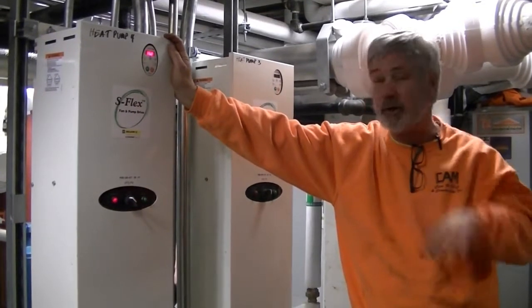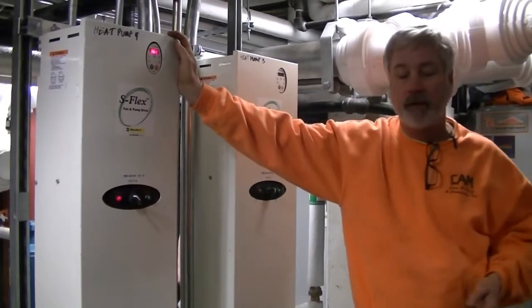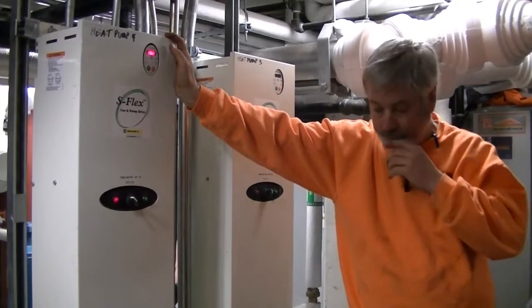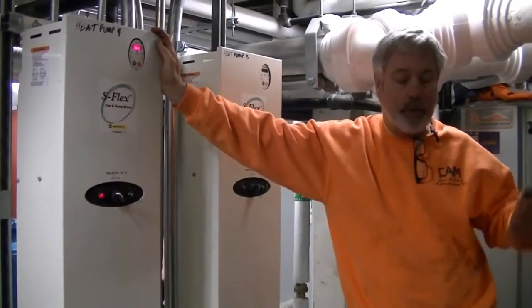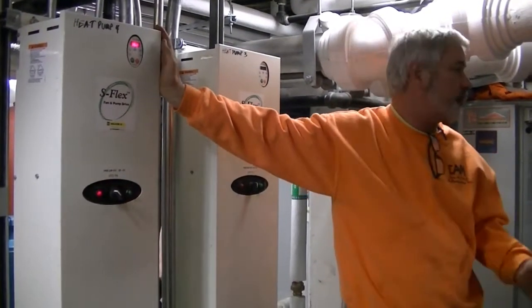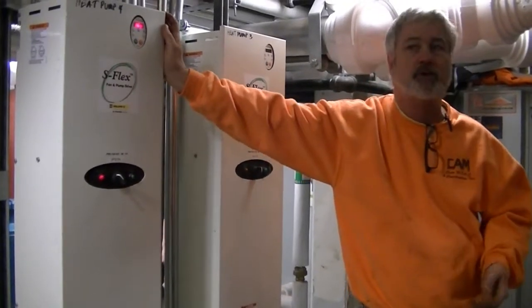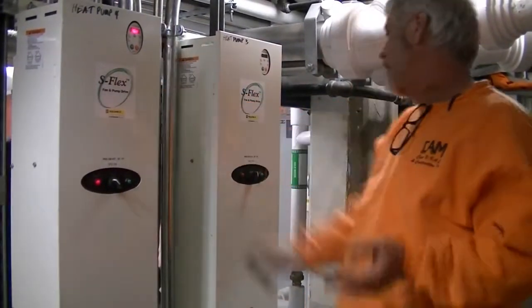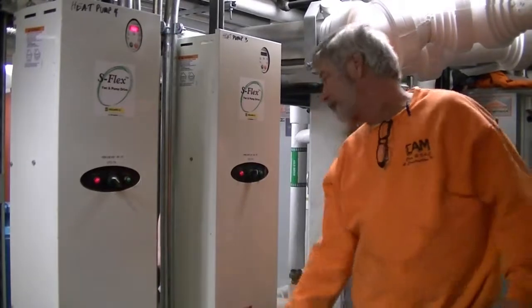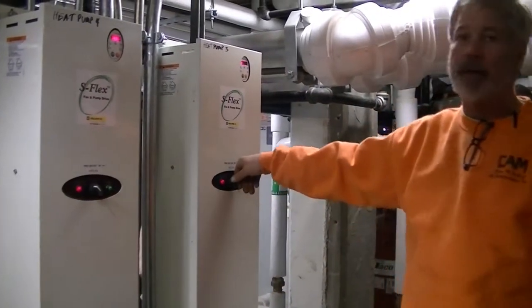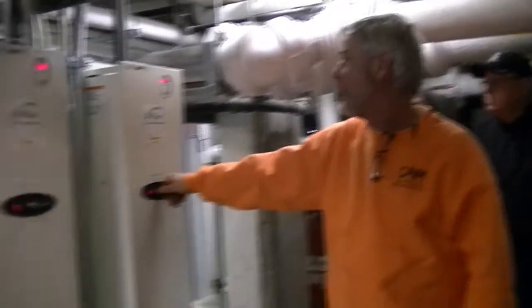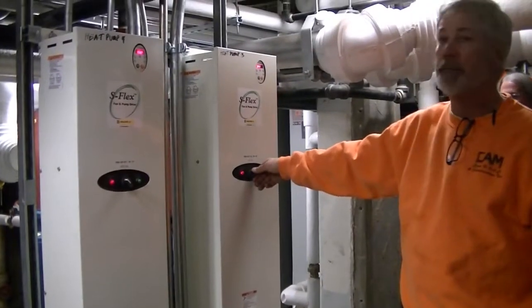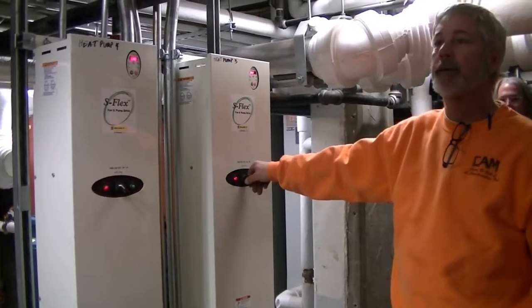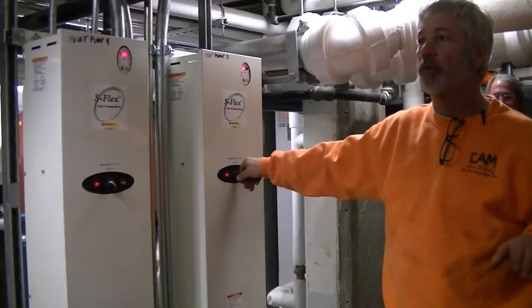Again, your control contractor is going to go over that with you later. Now, for some reason your control system crashes or something malfunctions and you need to run pumps, there is the ability to bypass the pump. You can put it in bypass and the pump goes to 60 hertz right away. It stays there, it doesn't move.